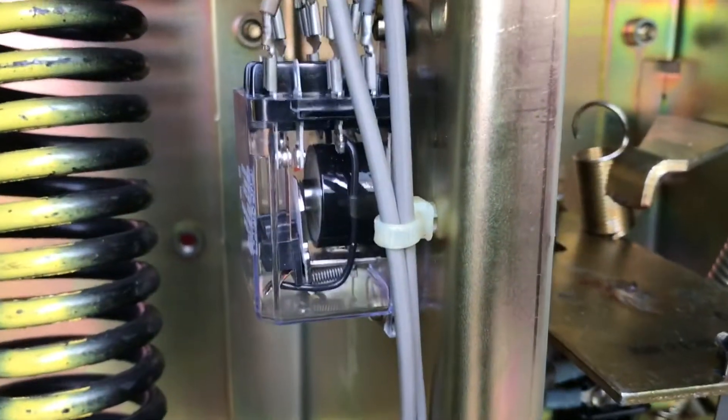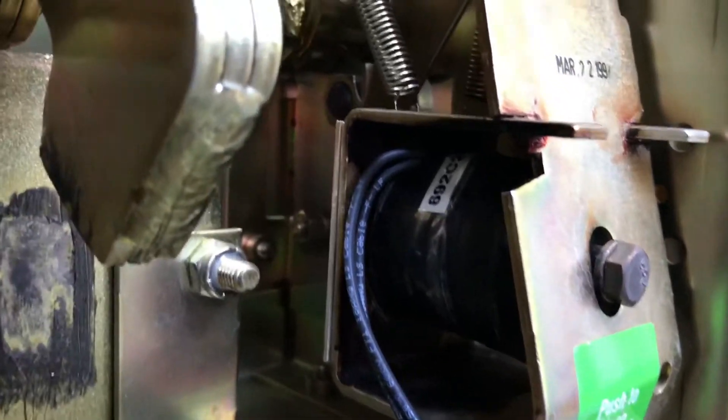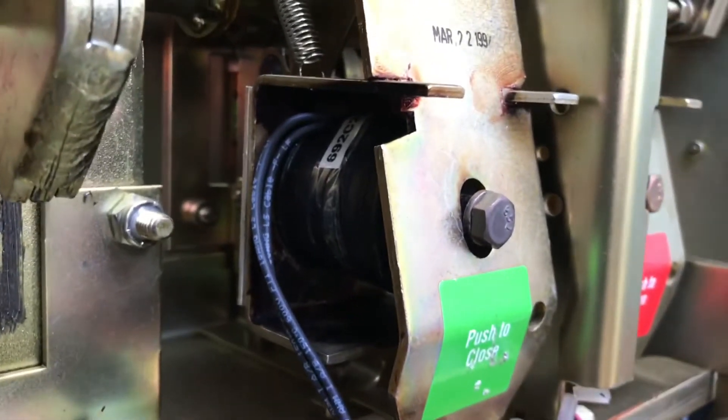We can see the anti-pump relay is in good condition. There is a lot of nastiness around this coil, but the coil is in good condition and working as intended.